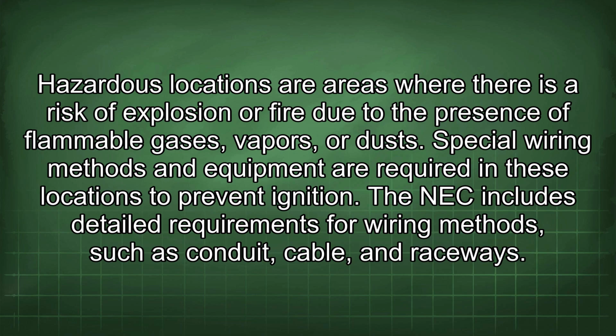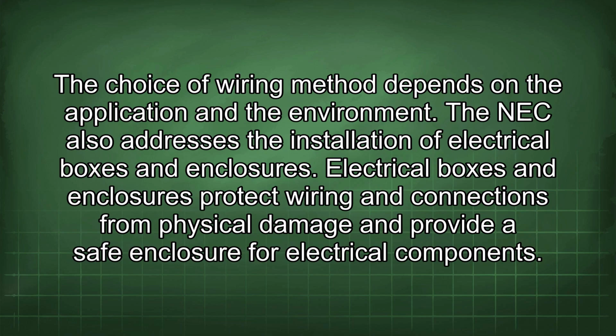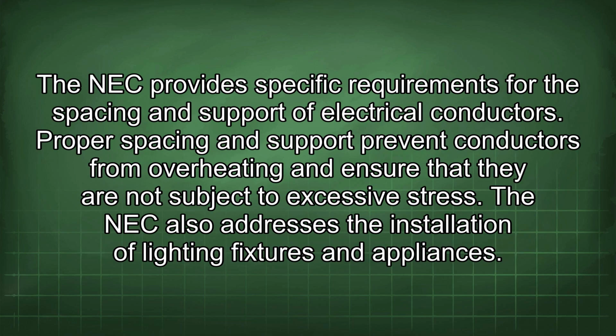The NEC includes detailed requirements for wiring methods such as conduit, cable, and raceways. The choice of wiring method depends on the application and the environment. The NEC also addresses the installation of electrical boxes and enclosures. Electrical boxes and enclosures protect wiring and connections from physical damage and provide a safe enclosure for electrical components. The NEC provides specific requirements for the spacing and support of electrical conductors. Proper spacing and support prevent conductors from overheating and ensure that they are not subject to excessive stress.